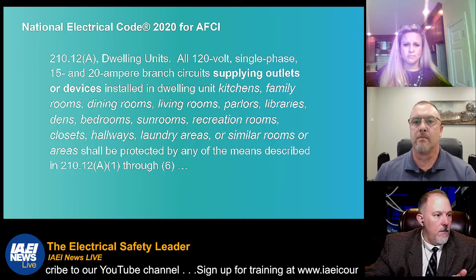Initially, these devices were only required to protect bedroom circuits. Over time, we learned that these devices actually work and do their job, so if we're going to protect bedroom circuits, we might as well protect the dining room, family room, and closets. The next slide lays out all the different areas of the home required for AFCI protection per the 2020 code: family rooms, dining rooms, living rooms, parlors, libraries — basically almost every room of the house is required to be AFCI protected.